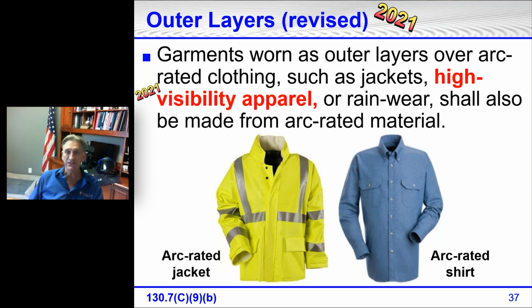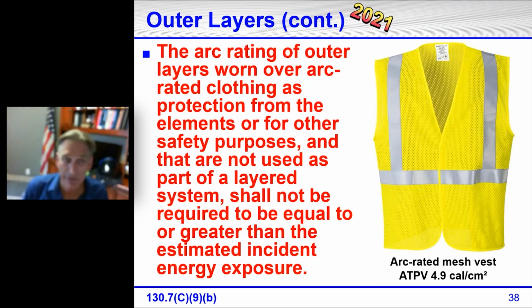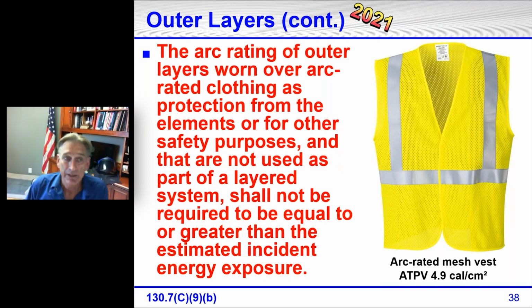Well, let's look at something else that was changed in the 2021 edition. This was added: the arc rating of outer layers worn over arc rated clothing as protection from elements or for other safety purposes, and that are not used as part of a layered system, shall not be required to be equal to or greater than the estimated incident energy exposure.